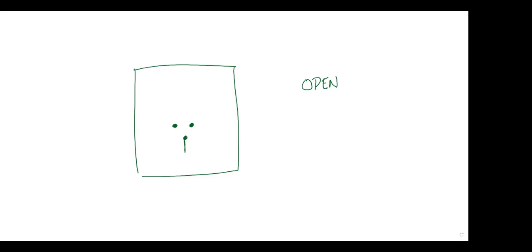When I say visual open, the definition is air between contact points. I have to see air in between the two. Open the bus side disconnects and line side disconnects. When those open, I can see air in between. Got it. Okay, good deal.